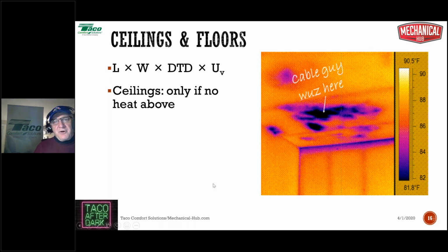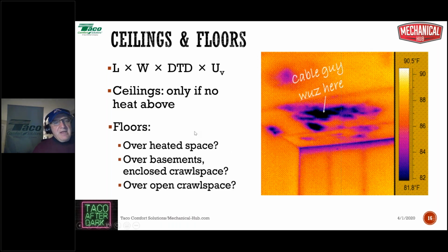For our example, we're presuming a heated space above, but the math is the same: length, width, DTD, U value. If half the ceiling has heated space above and half doesn't, you only figure heat loss for the half that doesn't. So that's how you approach a ceiling - only if there's no heated space above.